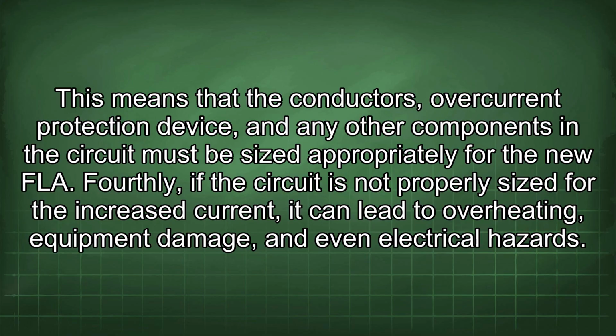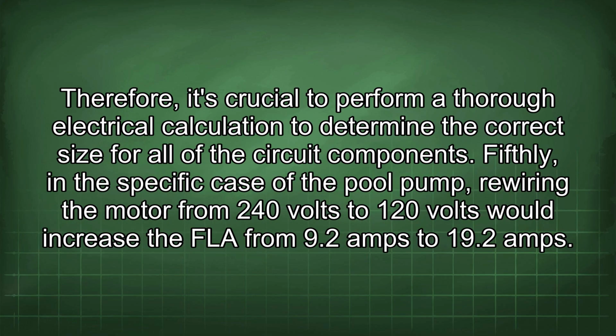Fourthly, if the circuit is not properly sized for the increased current, it can lead to overheating, equipment damage, and even electrical hazards. Therefore, it's crucial to perform a thorough electrical calculation to determine the correct size for all of the circuit components. Fifthly, in the specific case of the pool pump, rewiring the motor from 240 volts to 120 volts would increase the FLA from 9.2 amps to 19.2 amps.